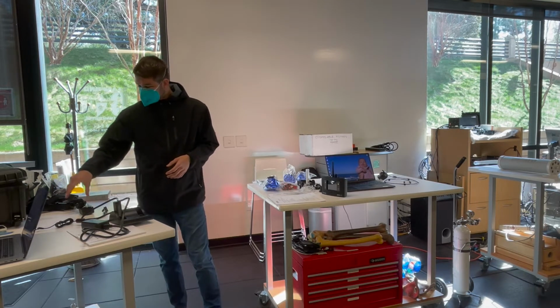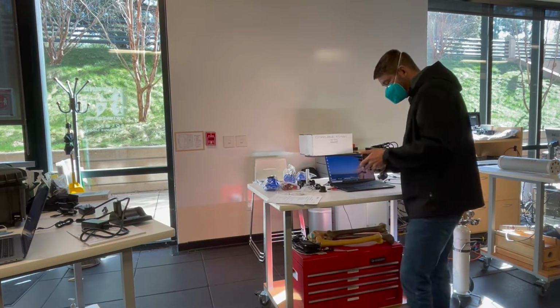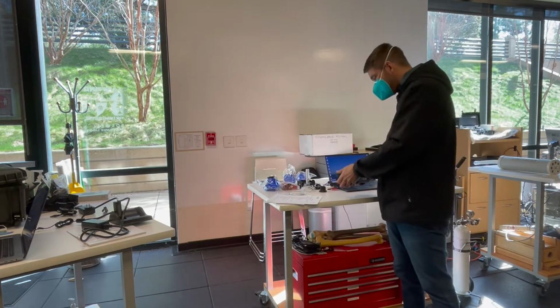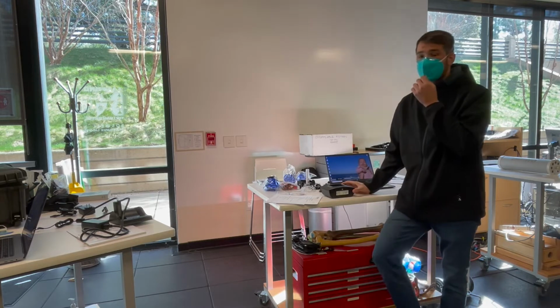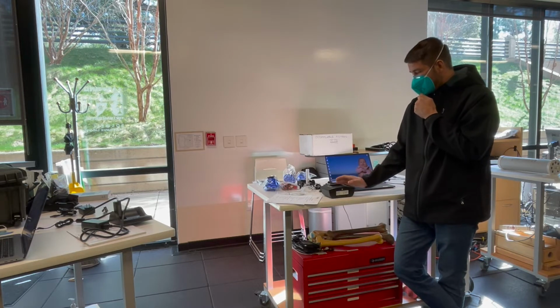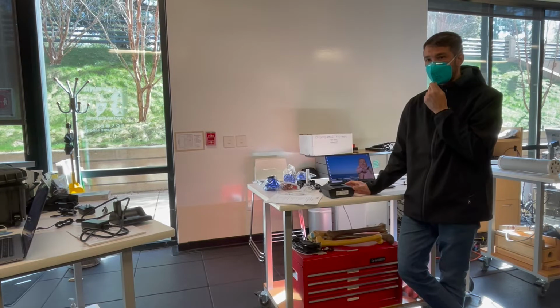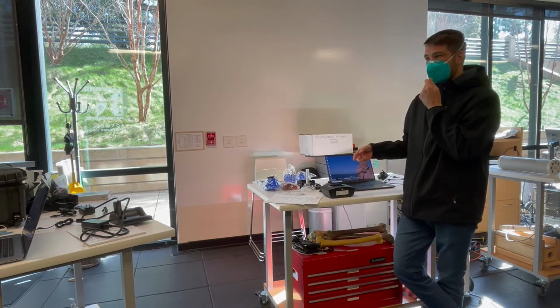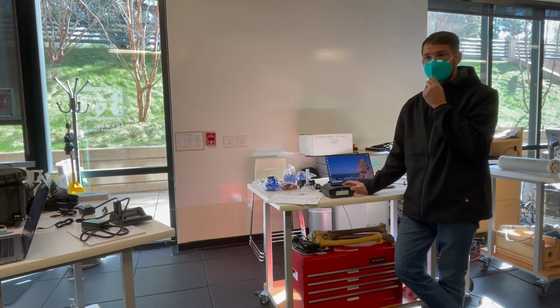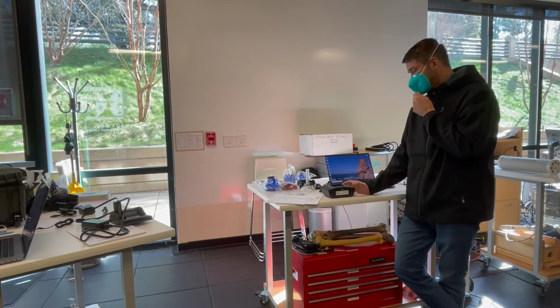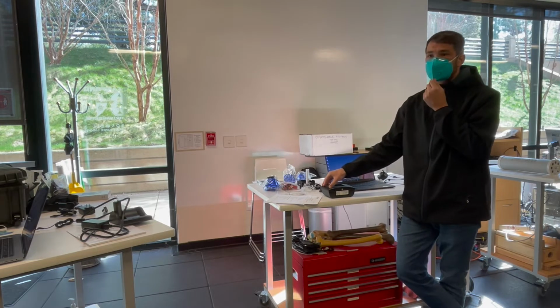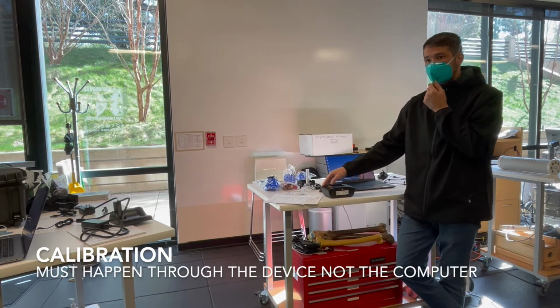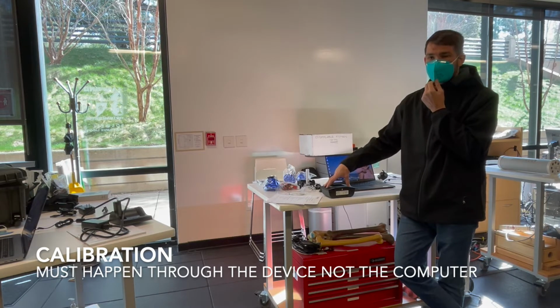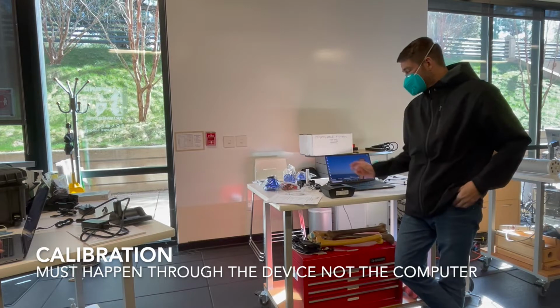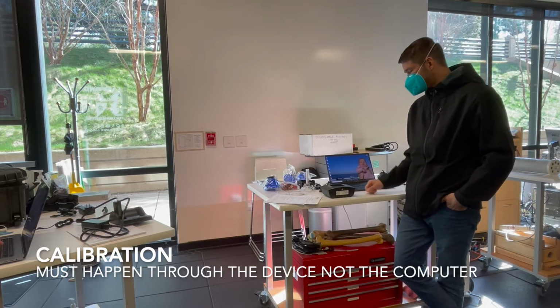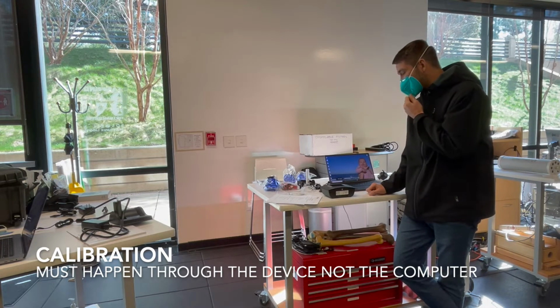What's a little interesting about the way that this is set up is that you can run everything standalone without the computer, or you can run everything through the computer, either Bluetooth or plugged in via USB. The only thing that you can't do with this system through the computer is calibrate it. So it has to be calibrated directly on the device itself. So before we even connect to the software or do anything like that, we'll just start running through calibrations.